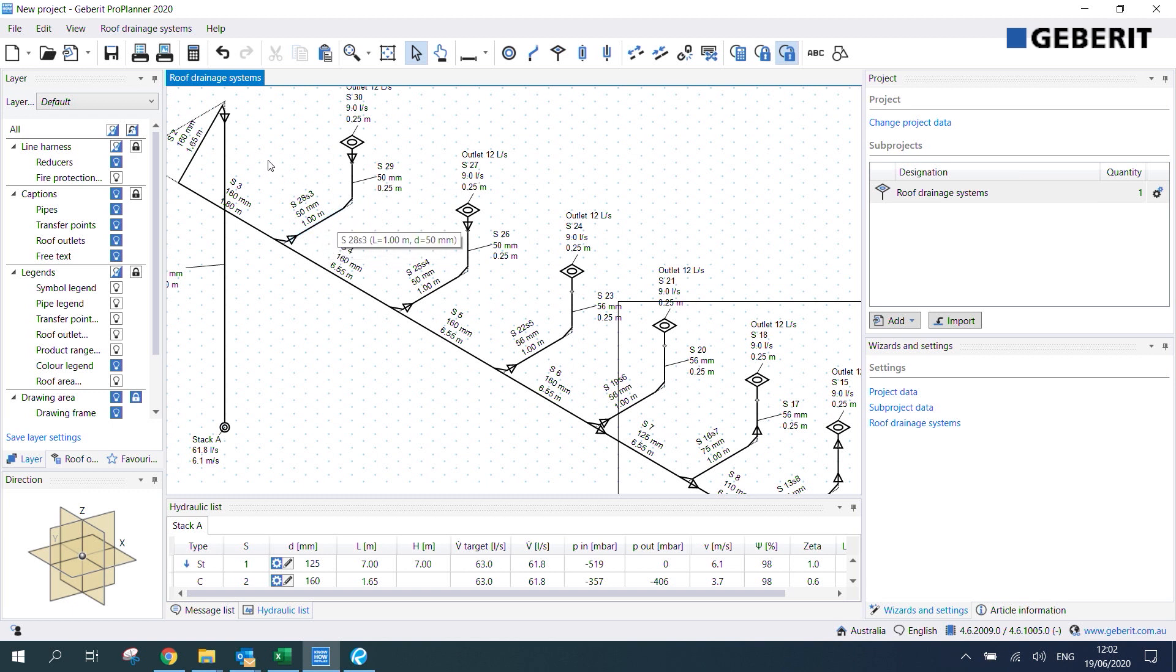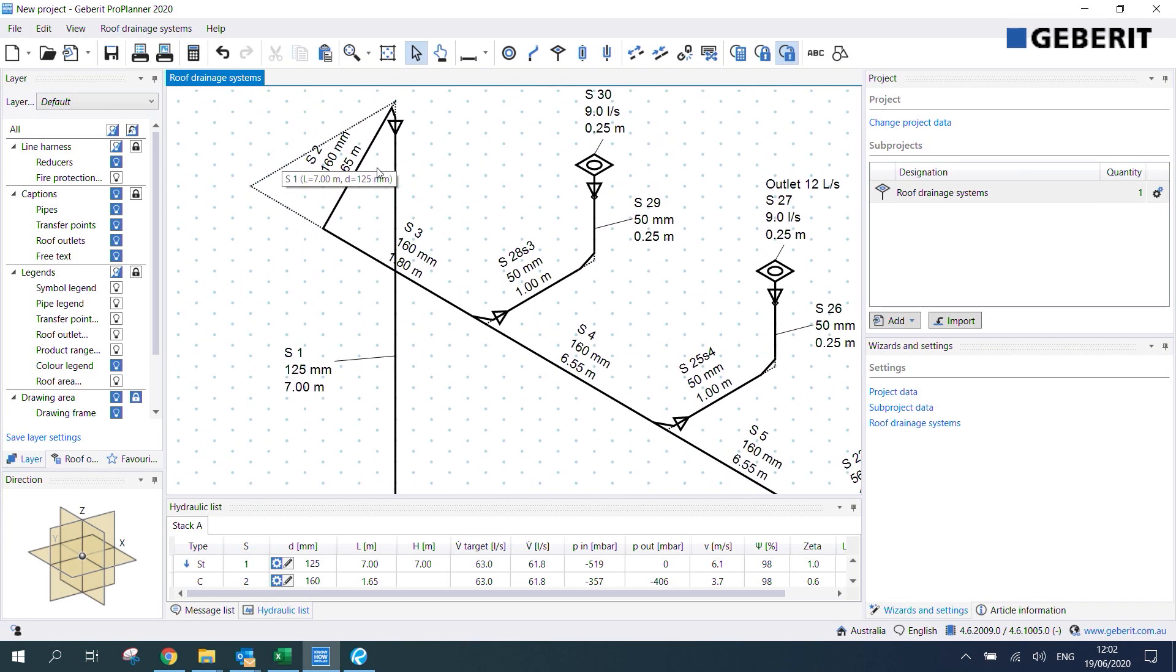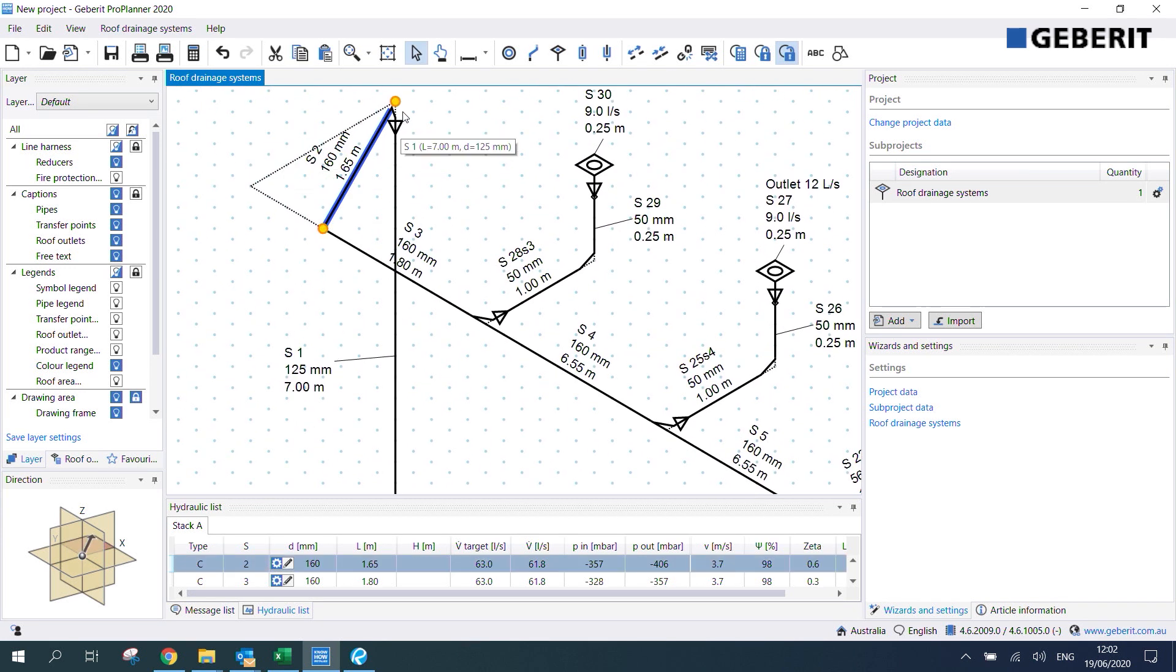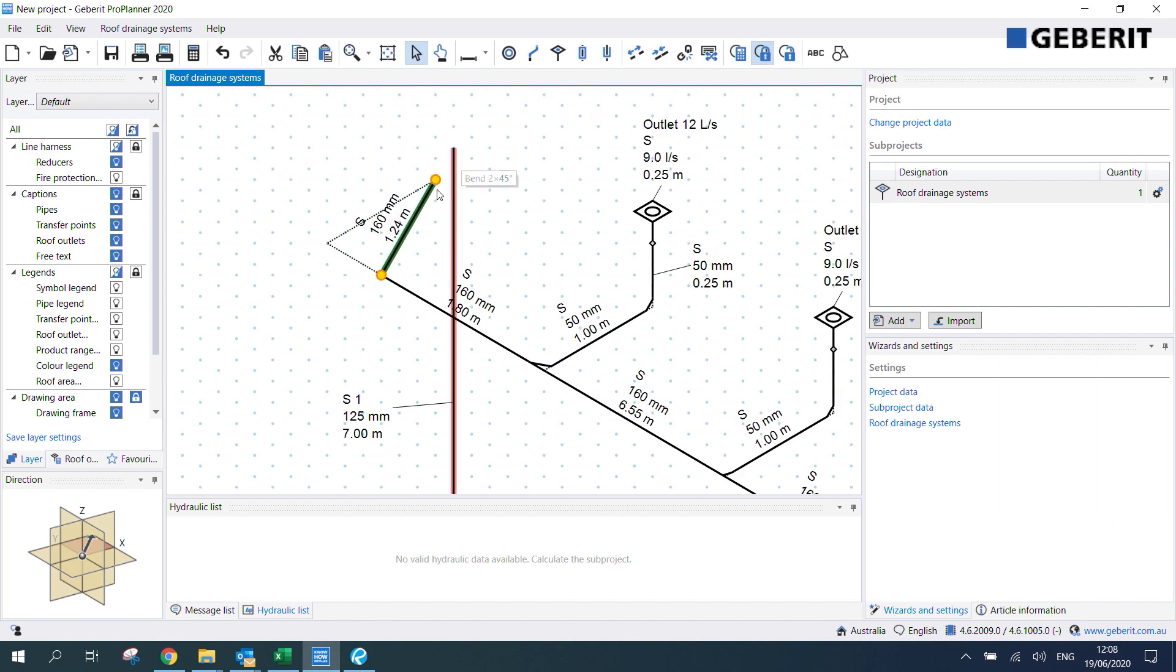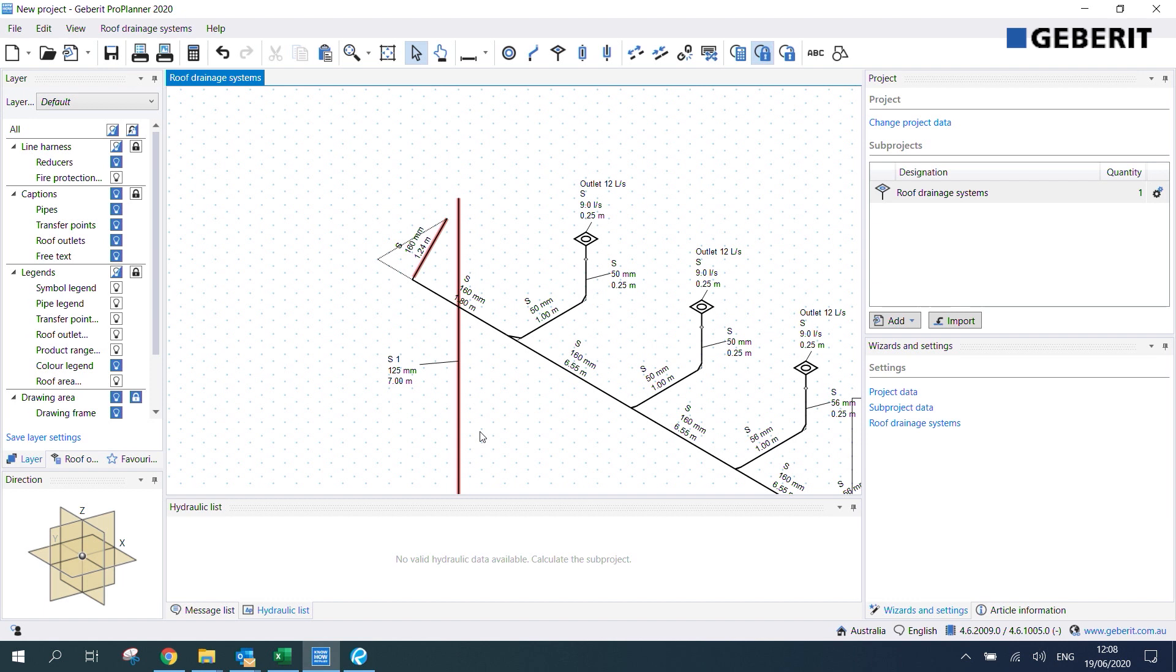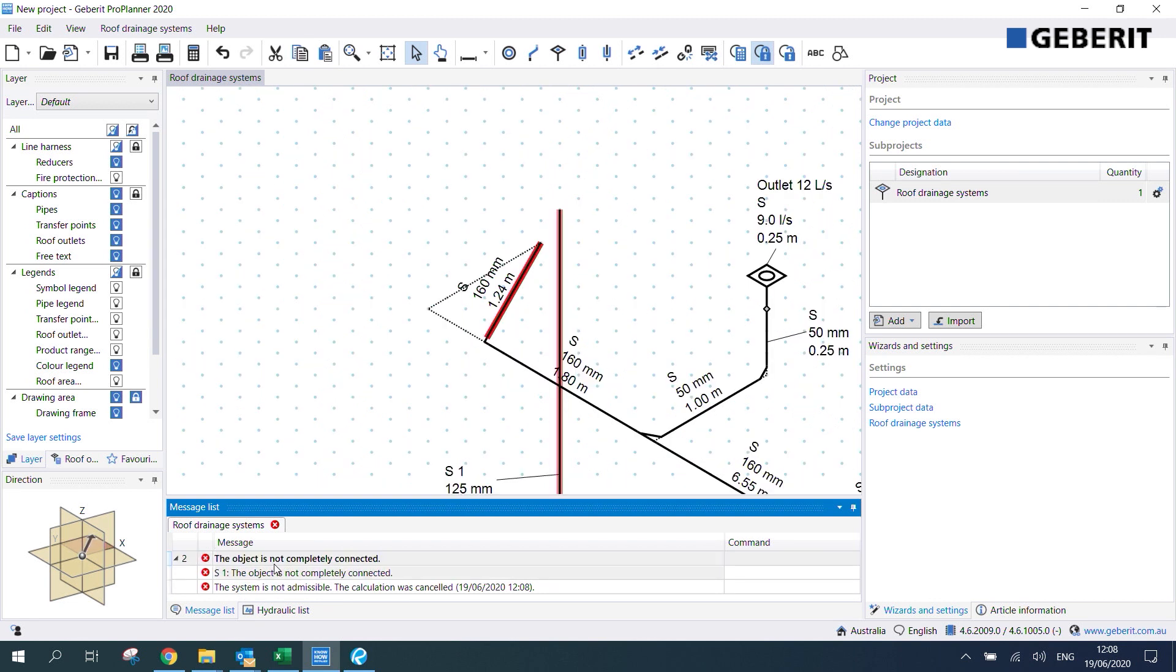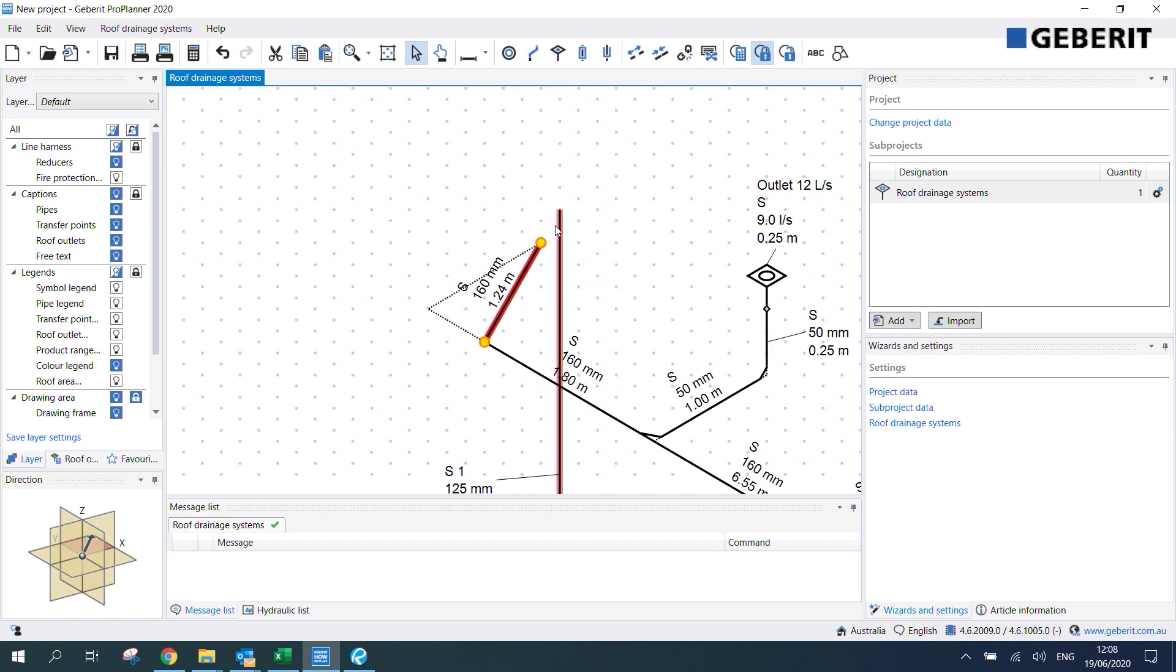Now I'll just demonstrate what happens if we've made a mistake in the drawing. Let's say we forgot to connect this pipe section correctly. If we hit optimize we'll get this red highlighting which shows that we've made a mistake somewhere. We can review where we've made this mistake by going into the message list. We can see that it says the object is not completely connected. If we click on this it'll take us straight to where we've made that mistake and we can fix it up. I'll fix it by connecting that there and then we can click optimize diameters again.